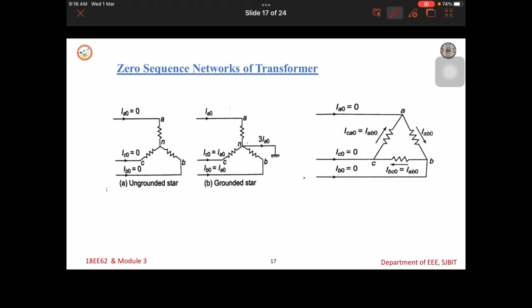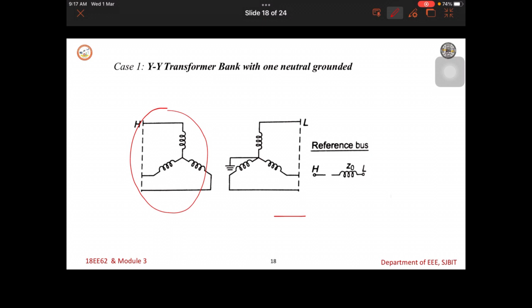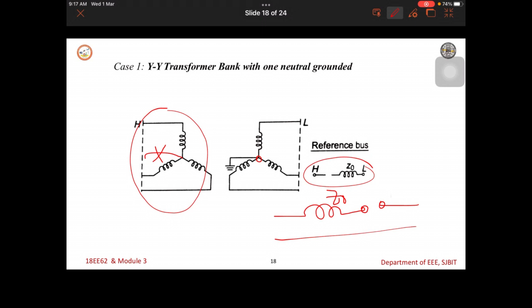Next we will see one more. We will see the transformer in star star fashion. If this is the case, then the primary winding won't have any option of carrying the neutral current, as the neutral wire is absent here. Here the neutral wire is present, but a path should be provided on both sides. Therefore, the zero sequence network is shown here.